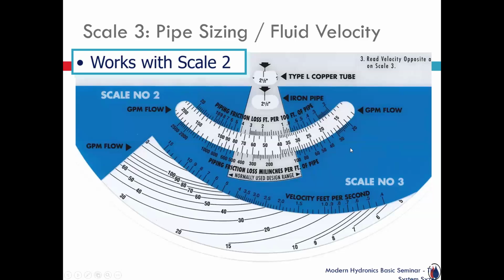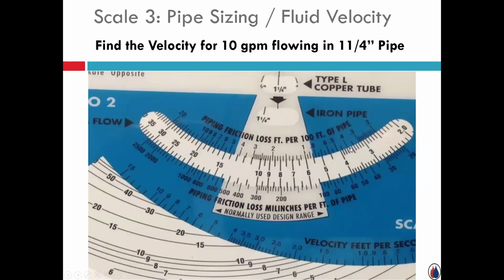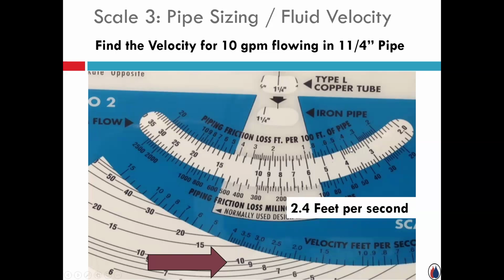Real quickly, looking at scale 3, it's right below scale 2. So it does work. This is the one time where the two scales work together. Find the velocity at 10 GPM flowing in that 1¼ inch copper pipe. Up here in scale 2, I had 1¼ inch lined up and I saw the 10. Now I'm going to glance down to scale 3 and find the GPM in that white band. Where does that 10 intersect the velocity feet per second scale? It's just about 2.3, 2.4 feet per second. So fast enough, not too fast.